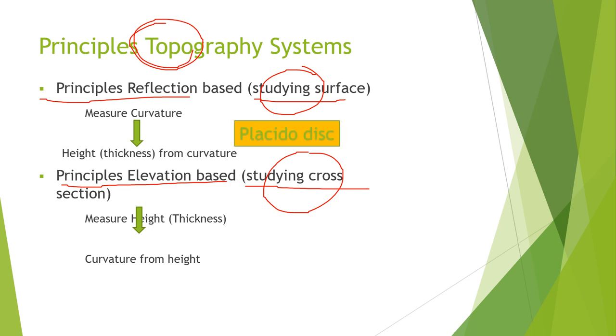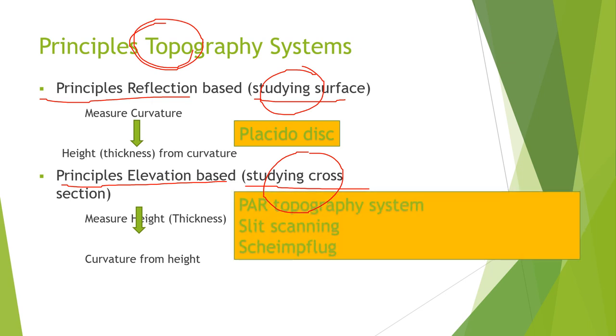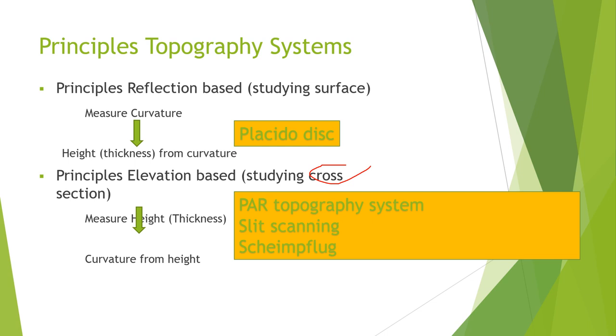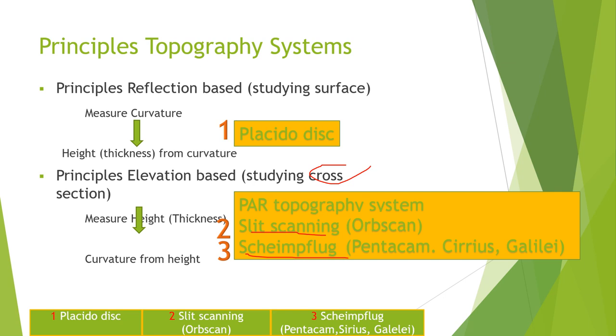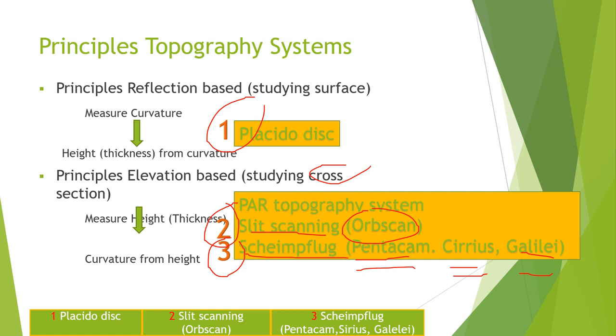The reflection-based system is the Placido disk, while the cross-section-based systems are the slit scanning system and the Scheimpflug system. In normal practice we have three basic principles: the Placido disk, the slit scanning which is used in Orbscan, and the Scheimpflug camera which is used in Pentacam, Sirius, and Galilei. We are going to talk about these three basic principles one by one.